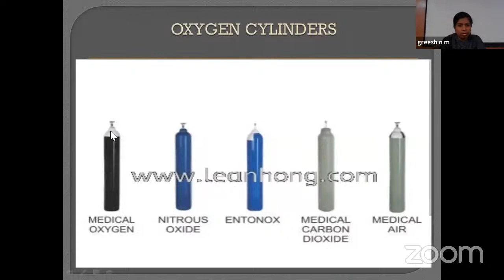So there are different cylinders in our medical field, and the oxygen cylinder has a black body with a white shoulder. These are different oxygen cylinders, and up to E is considered smaller cylinders, and the remaining are the bigger cylinders. There can be many types of valve. I'm going to talk about the pin index and the bullnose type of valve. This is the pin index, and this is the bullnose type of valve, which has a hand wheel.